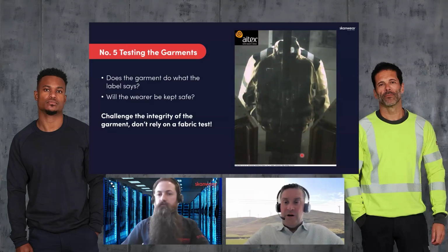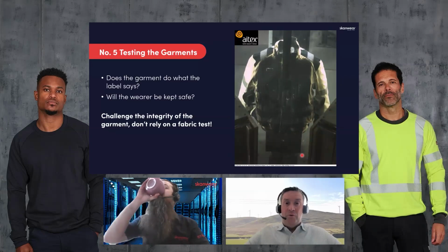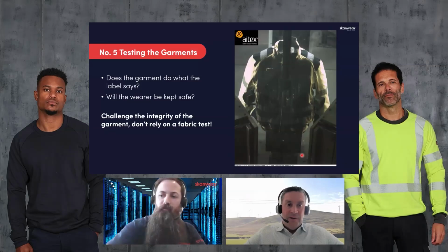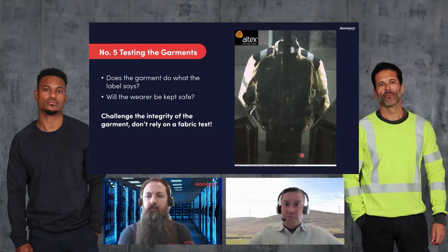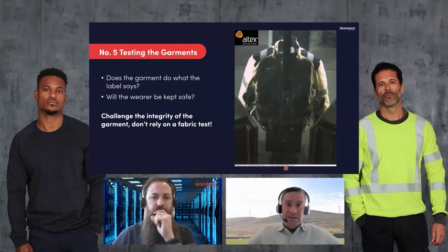So if your garments are actually arc flash certified in Europe, so not a -1-2 or a -1-1 standard, then a 61482-2 standard, which means it's been certified and it's had a mannequin test like you see in the video there. And that's to make sure that in actual fact, when the garment is made together as a combination, it's actually going to stay intact. After it's happened, you're going to be able to undo zippers and Velcro fasteners, etc., and actually get out of the garment, because the garment would still retain an amount of warmth.